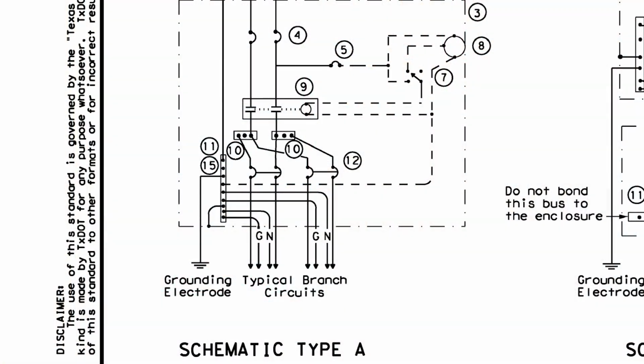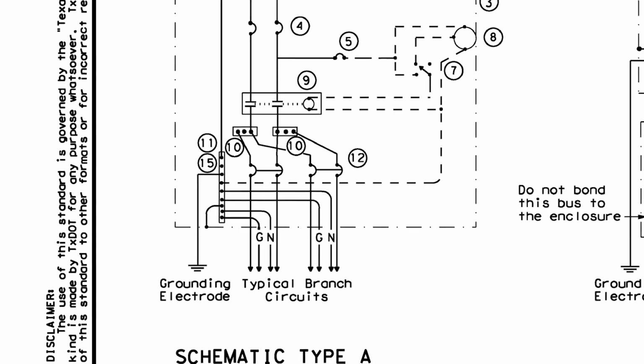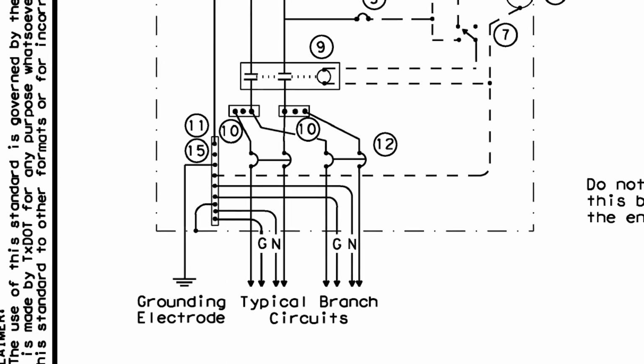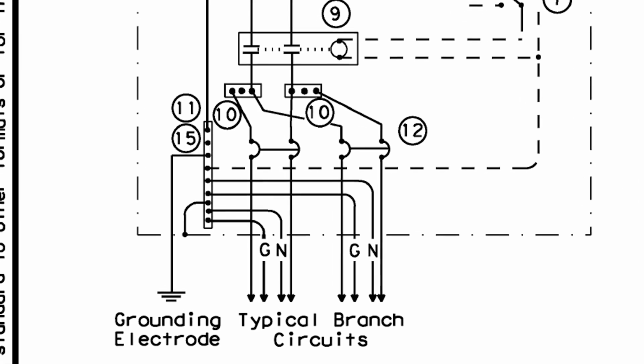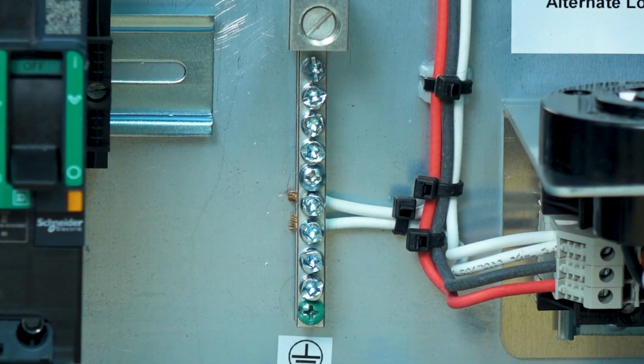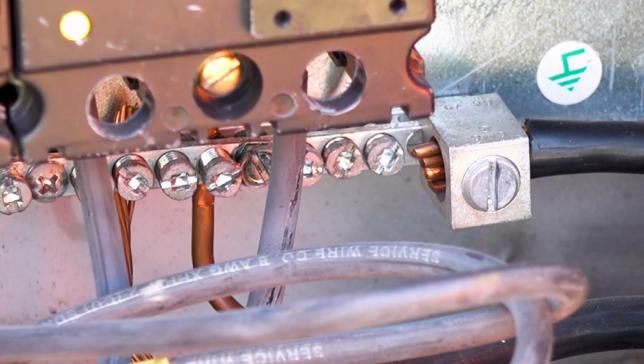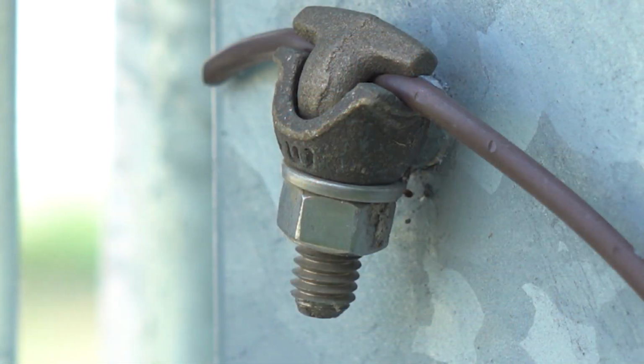The schematic diagram for the Type A service shows a single grounding bus bar, to which are connected the grounding electrode conductor, the ground service entrance conductor, current-carrying grounded conductors from the branch circuits, and the equipment grounding conductors associated with branch circuits. All white insulated neutrals will connect to the grounding bus. The solid number 6 bare copper grounding electrode conductor connects to it also, the other end of which is connected to the ground rod or tank lug on the steel pole as shown on ED7 and ED8.